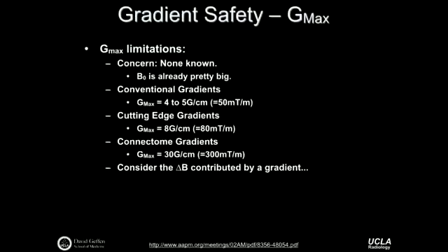And you'll appreciate more and more maybe why gradient strength is important, but it nominally governs the speed at which we can image. And so stronger gradients can allow us to image more quickly in principle. There is a neuroimaging project called the Connectome project, and they have specialized gradient systems that go up to 300 millitesla per meter, so very, very high magnetic field strengths.